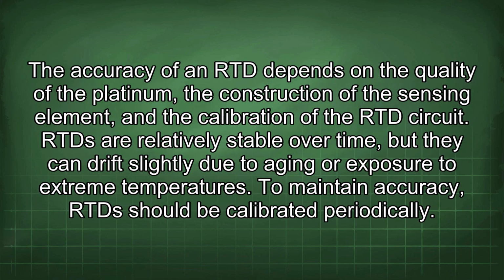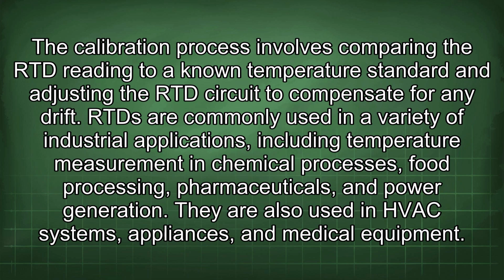The accuracy of an RTD depends on the quality of the platinum, the construction of the sensing element, and the calibration of the RTD circuit. RTD are relatively stable over time, but they can drift slightly due to aging or exposure to extreme temperatures. To maintain accuracy, RTD should be calibrated periodically. The calibration process involves comparing the RTD reading to a known temperature standard and adjusting the RTD circuit to compensate for any drift. RTD are commonly used in a variety of industrial applications, including temperature measurement in chemical processes, food processing, pharmaceuticals, and power generation. They are also used in HVAC systems, appliances, and medical equipment.